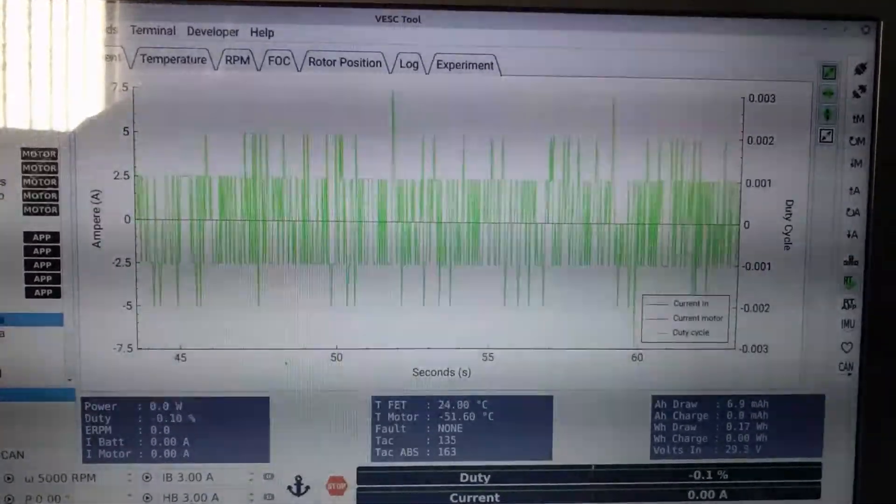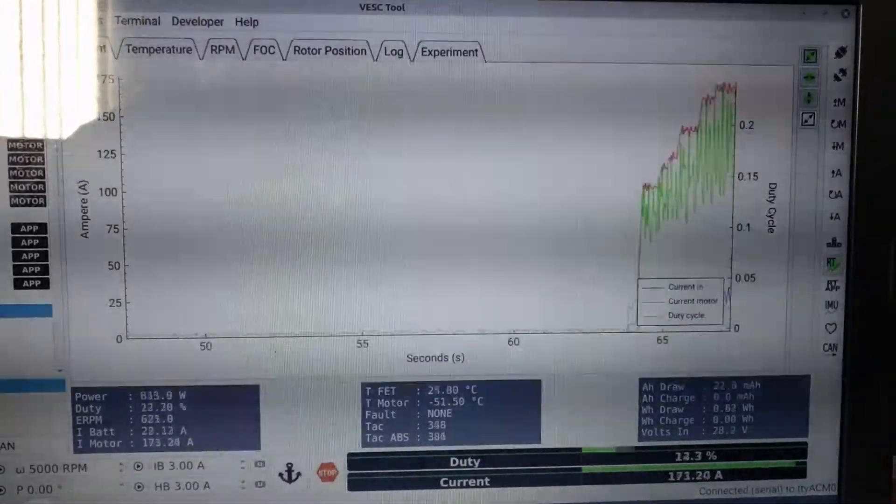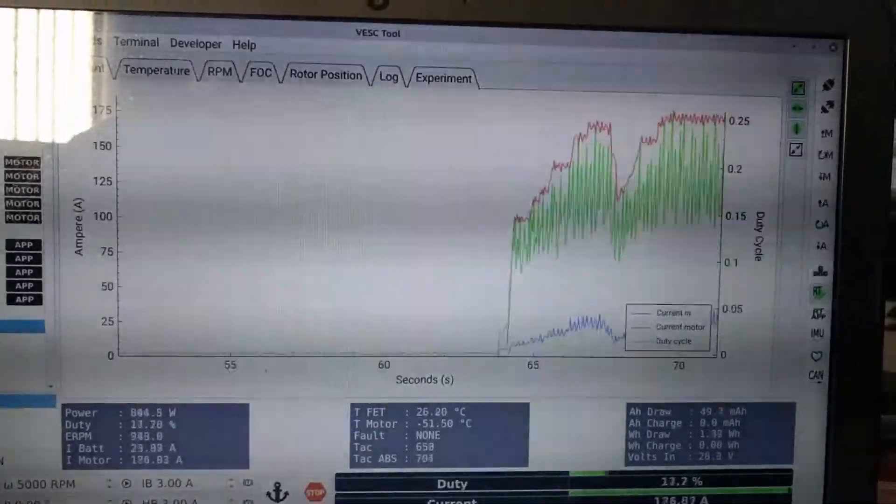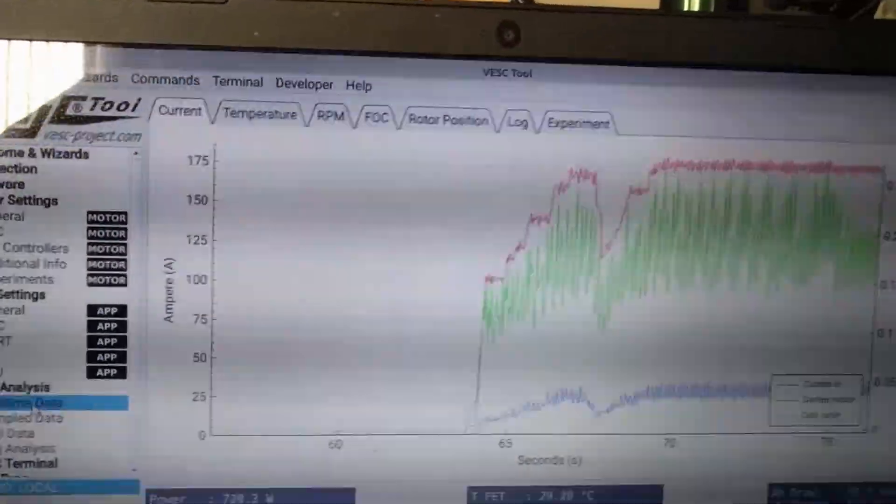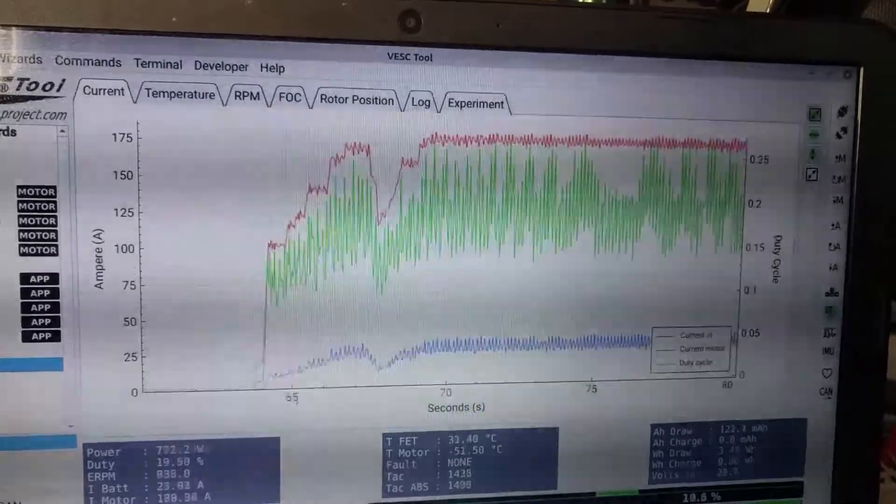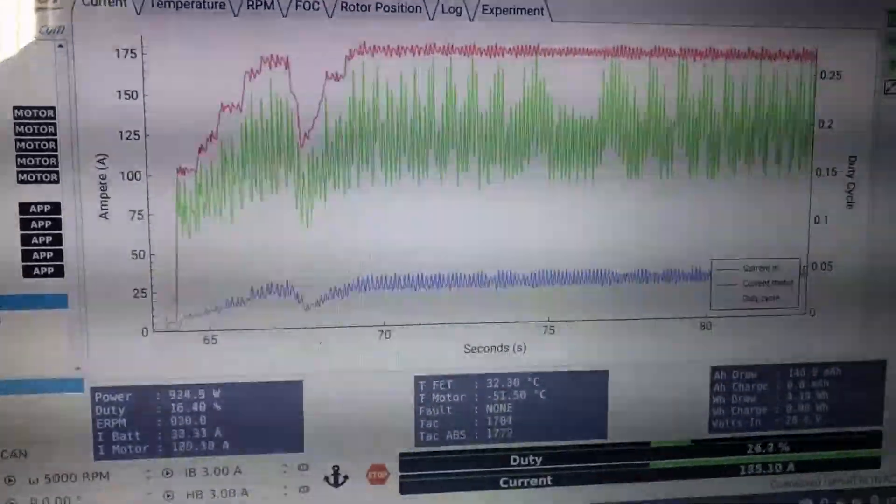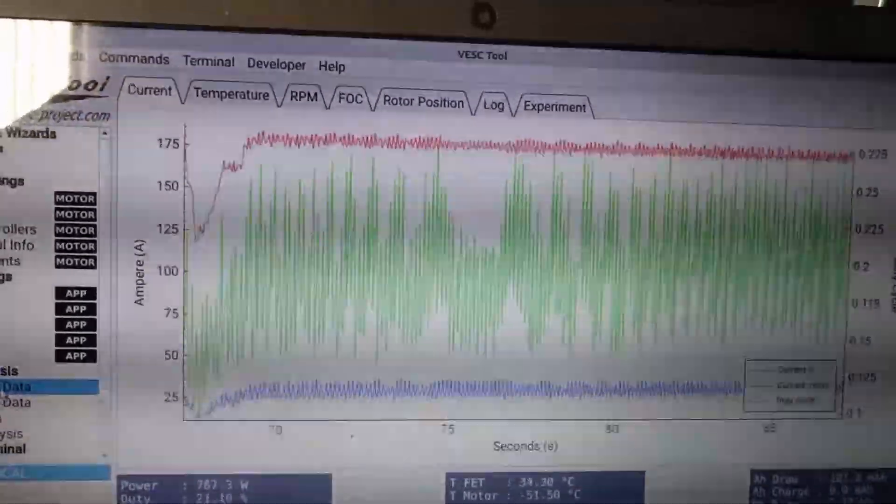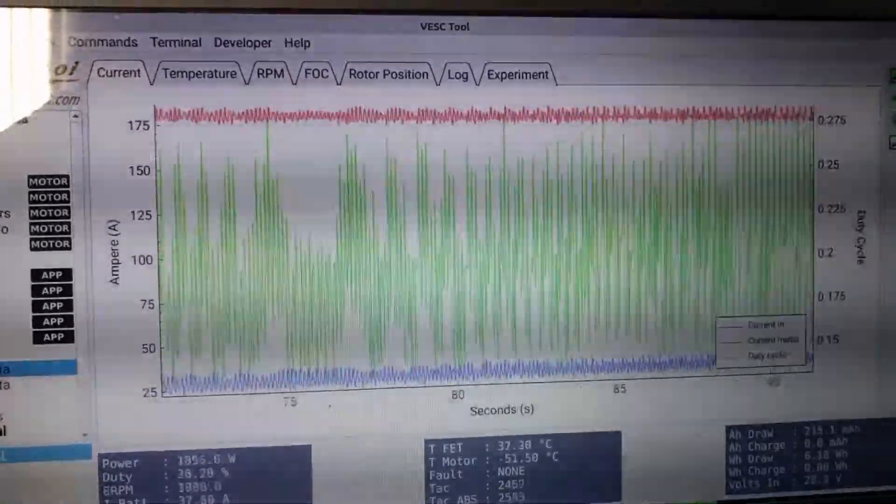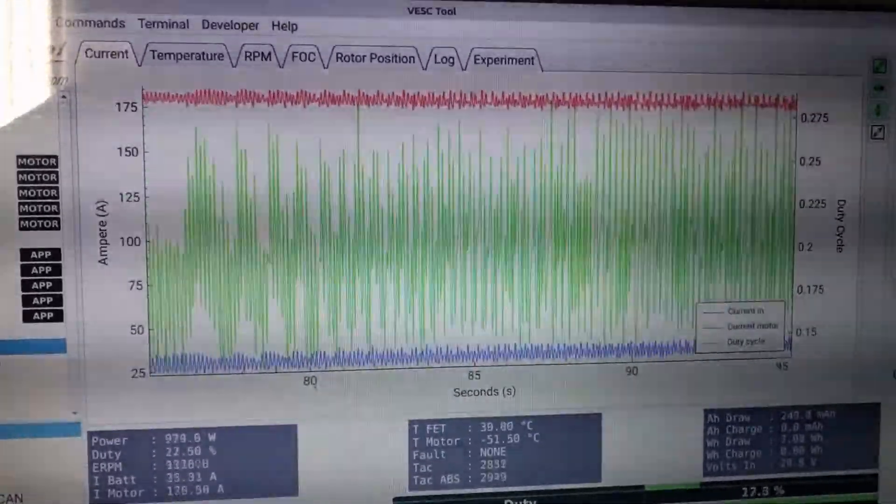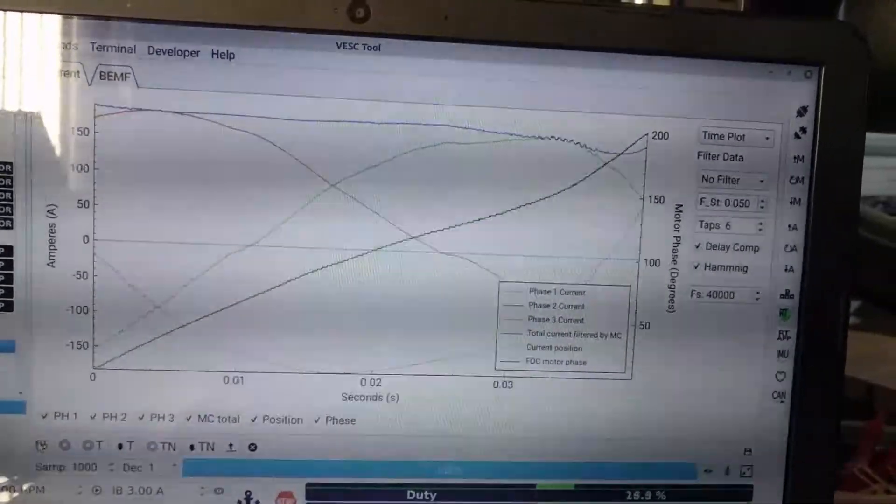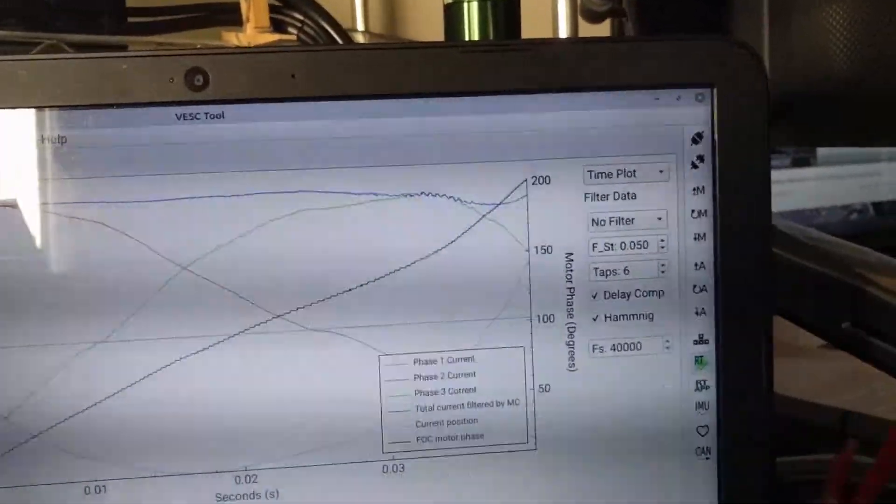Here's 180 amps. And here are those motors. I'm not very happy. It's pretty much a locked rotor scenario. It's not moving very far.